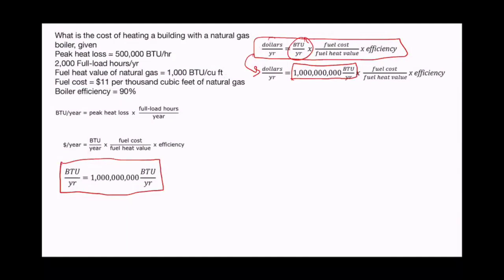We multiply that by our fuel cost. Our fuel cost is $11, but not $11 per cubic foot of natural gas. It's actually $11 per 1,000 cubic feet of natural gas. So we do 11 divided by 1,000, moving the decimal point 3 places over.